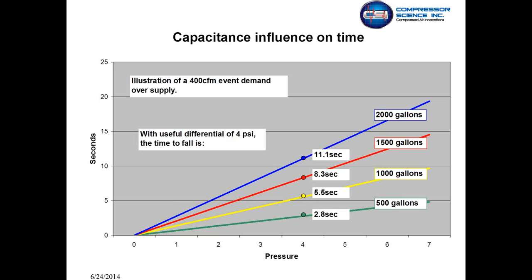So really, when we look into measuring the flow, we can actually isolate that demand out of the system and say, okay, this is happening. We have a 400 CFM event that's happening for 10 seconds. We know that if we put a 2000-gallon tank in there, we've got our differential of 4 PSI that we can deal with that event and remove it from the compressed air system without having to load a fourth or a third compressor. This is where we make a difference on the demand side savings, where we can say we can deal with storage, take that event out of the circuit, and stop that compressor from loading. Because once it loads, you've paid the demand charges, even if it unloads after a brief period of time when the event is satisfied.